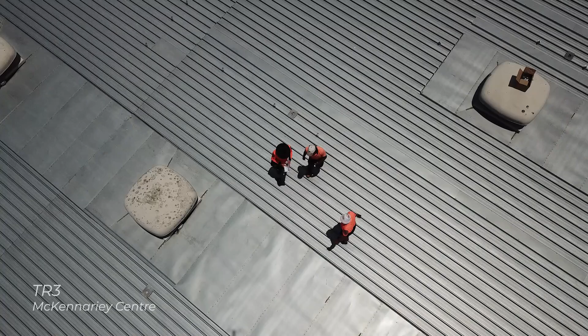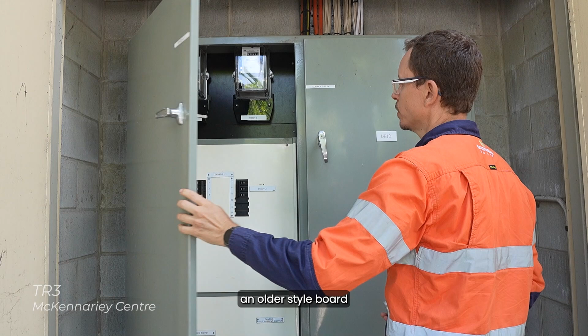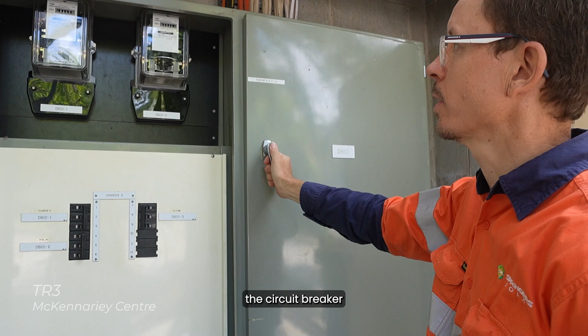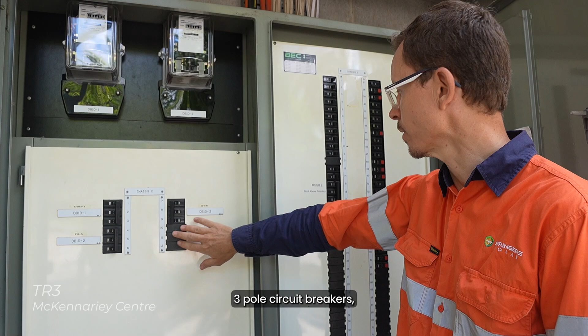So this is the switchboard we're connecting to for the TR3 building. It's an older style board with safety circuit breakers, so we weren't able to put a molded circuit breaker into this board because it just wouldn't fit. So we're going to split the system into two 50 kilowatt systems with two inverters, and put two 100 amp 3-pole circuit breakers, one there and one here, to cover the installation.